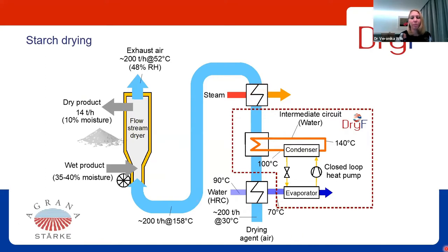We have integrated our heat pump right in the middle between those two heat exchangers, and we also use that heat recovery cycle as the heat source. We have here a temperature of 70 degrees roundabout, and so this is a very nice heat source for a heat pump. We have not integrated our DryFiciency heat pump directly into the airstream, but we have this intermediate water cycle here. We need that for measurement purposes mainly, to be able to have an accurate measurement of the heat supply temperature and the capacity that is provided by the heat pump. The heat pump has a heating capacity of about 400 kilowatt. This is 10% of the energy that is needed for the dryer. So this is a good size for a demonstration plant.